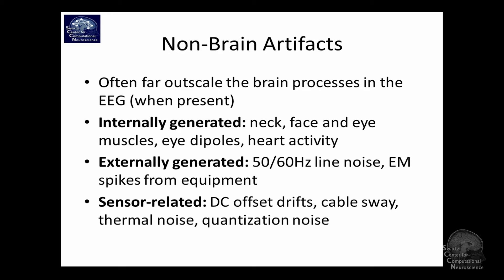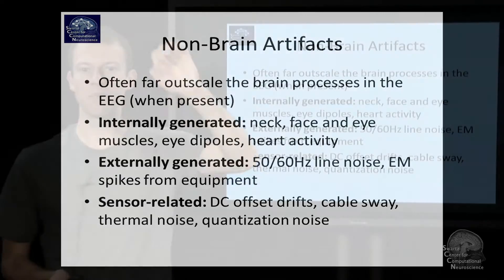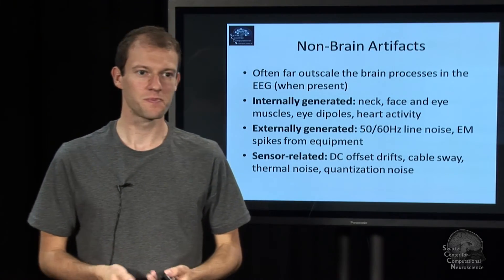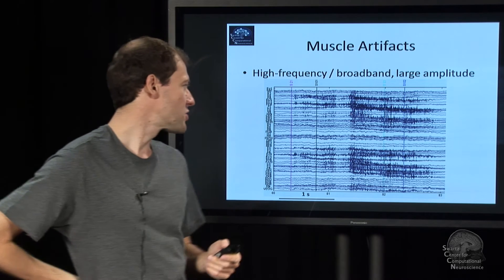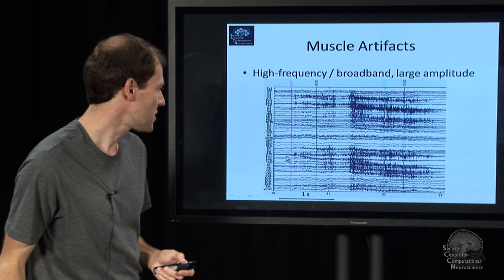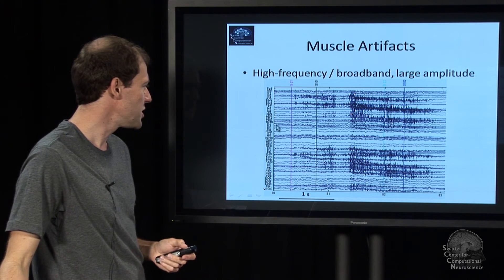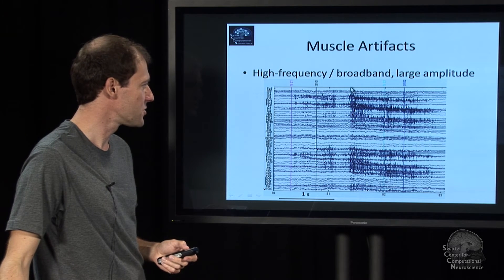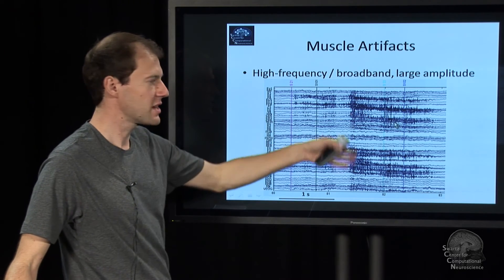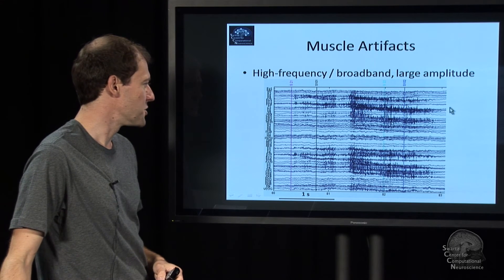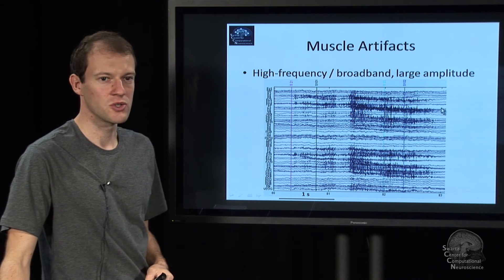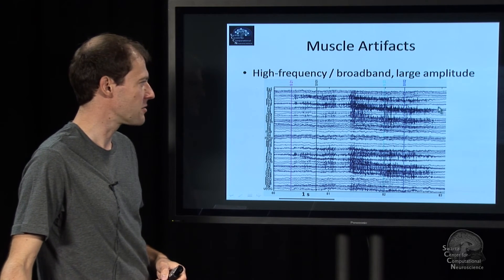And then there's so-called quantization noise of the analog-digital converter — it has a certain stepping, and so that's noise. Here are a couple of actual plots. These are muscle artifacts: you have some EEG at the beginning and then some muscle turns on. In the raw channels — here are the channel labels — you can see how strong these are with respect to EEG; there's nothing visible underneath.